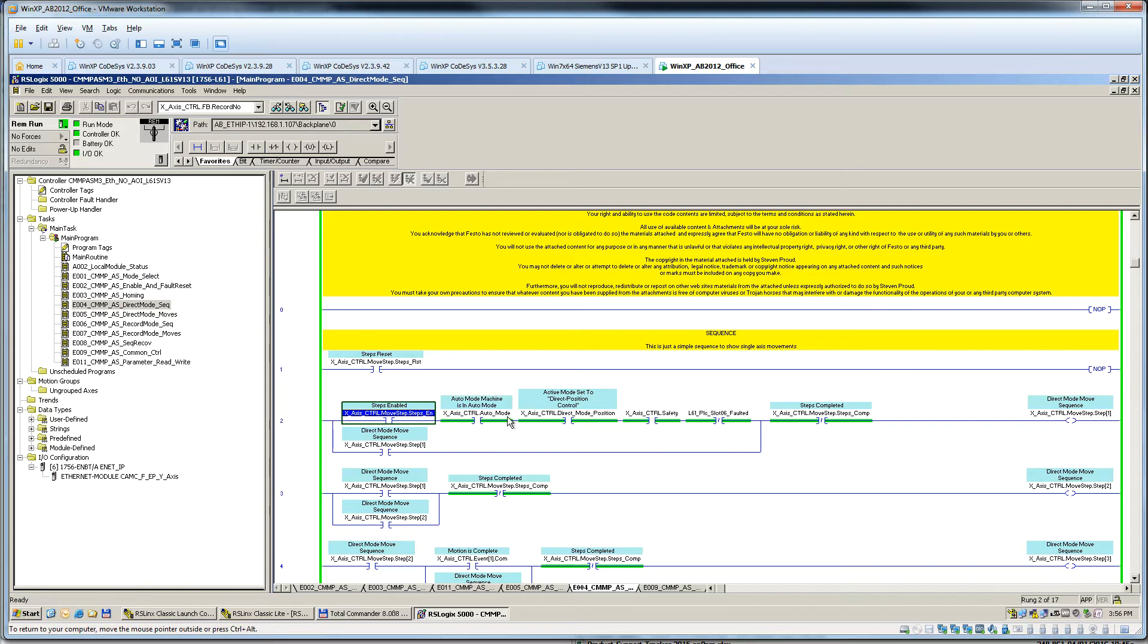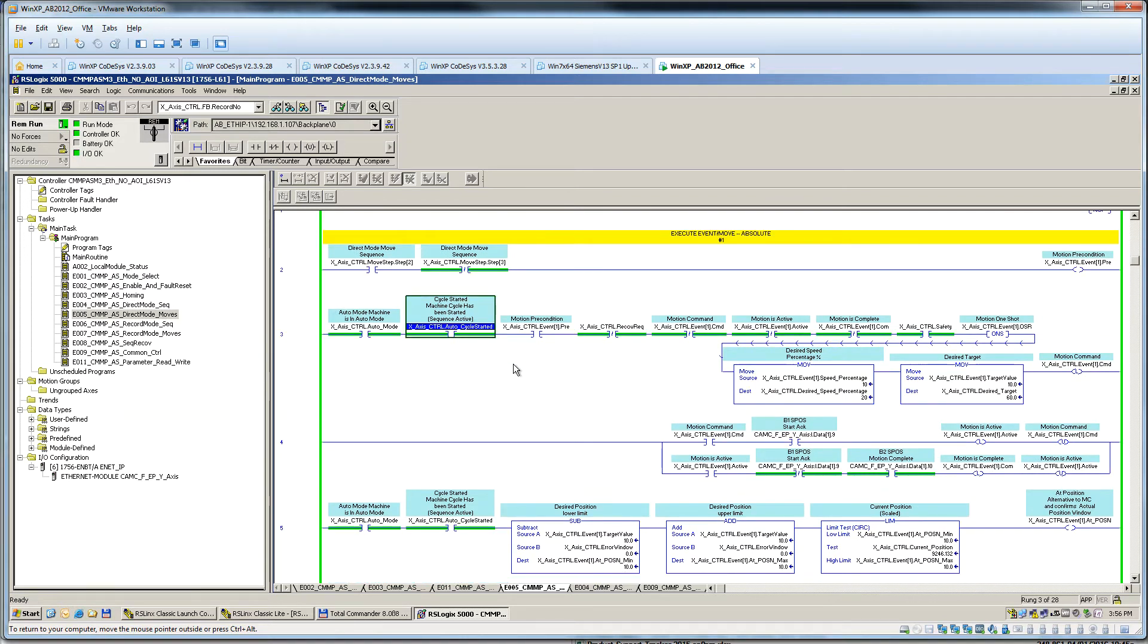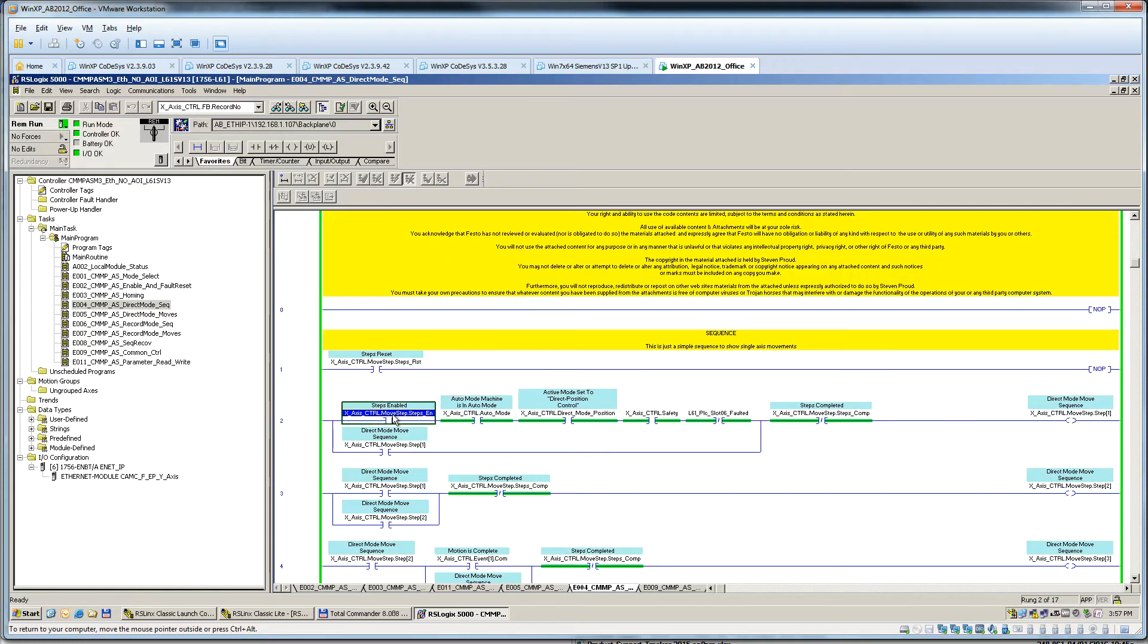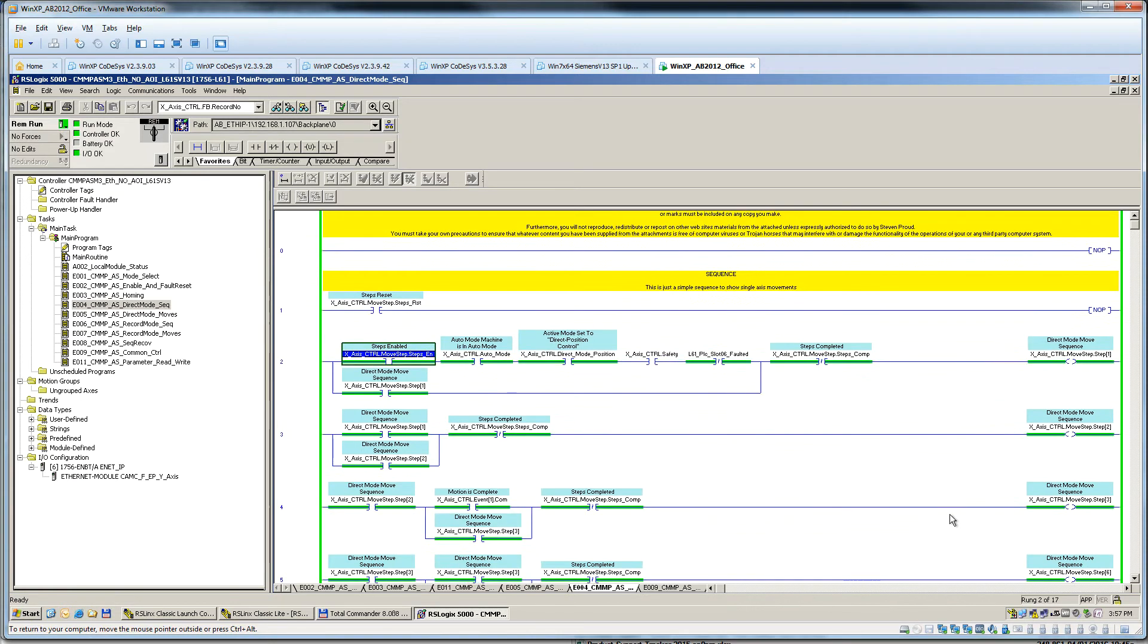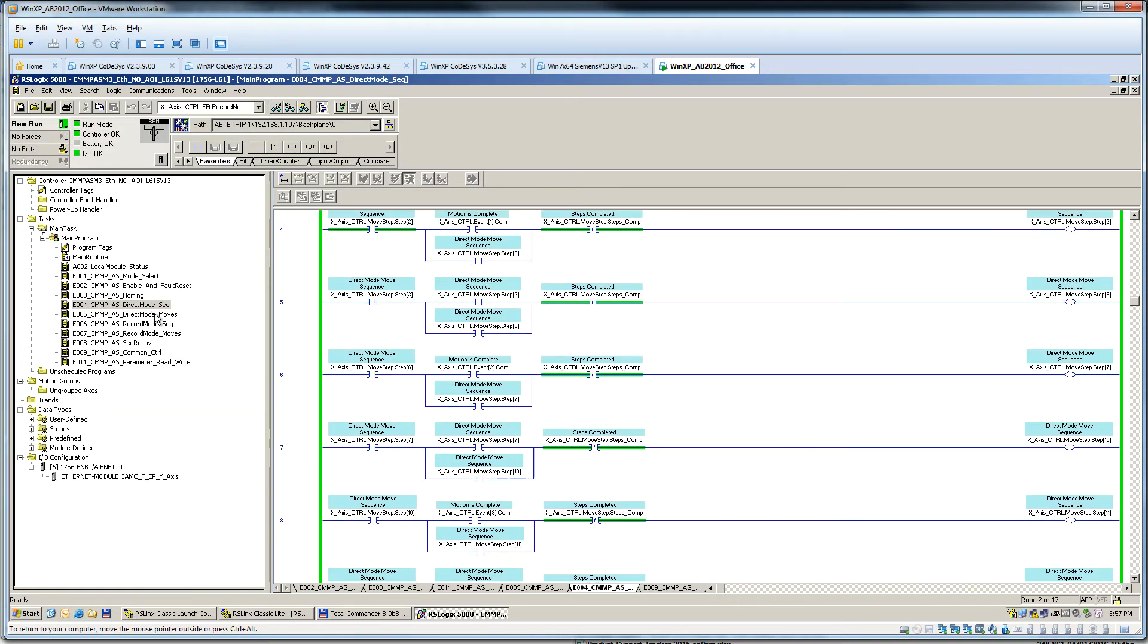That's how direct mode works. If I come in here, turn this auto mode bit on, this is a toggle right here. In the code, I have this bit and auto bit too. These are just toggle bits. Typically it's an auto mode on a machine and then there's a push button to say cycle start everything. That's auto mode. Turn the auto on. I've hit the cycle start button. Now I go into the steps here and I turn this bit on and it starts running through sequences.